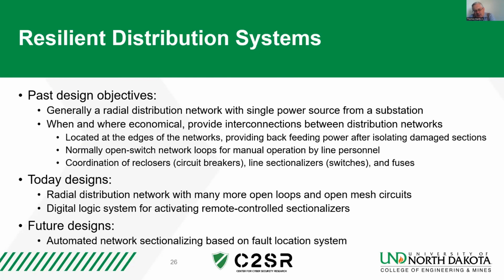So many utilities aren't quite ready to jump completely into a mesh type distribution network, but we can take incremental steps in closing loops in the system so that we can have loops that can be managed. Right now, there are some loops that are built into the system. We can take advantage of that, but those loops stay in a normally open state, and are only closed if part of another distribution section has lost service, and we can backfeed power into those. We'll show an example of that in just a second. Many of these have been hand operated by operators, actually linemen out in the field. The goal is to make this remote controlled, but now based with much better intelligence.